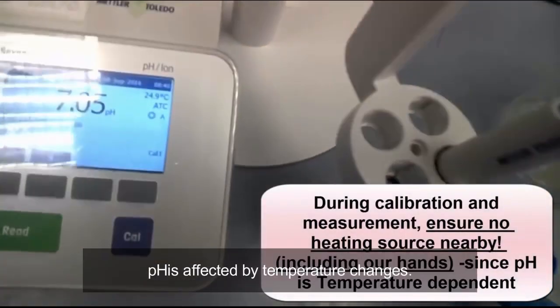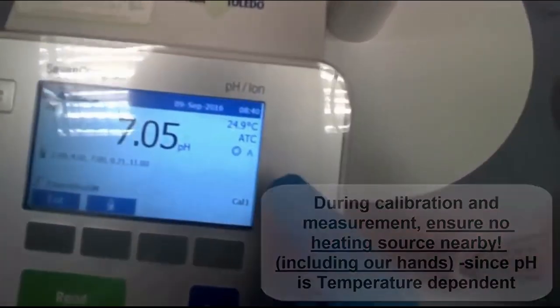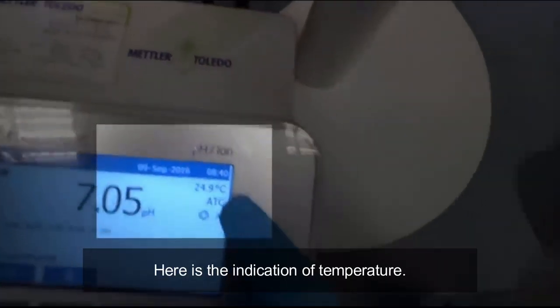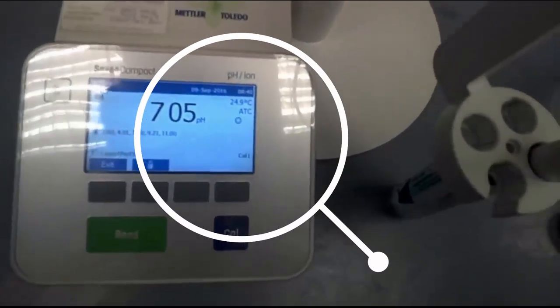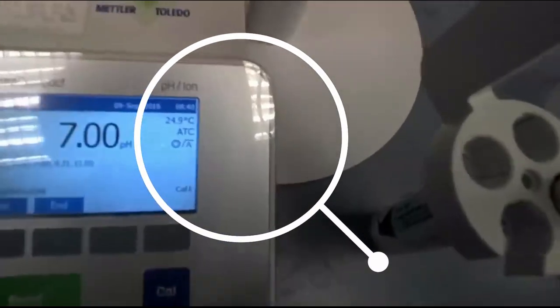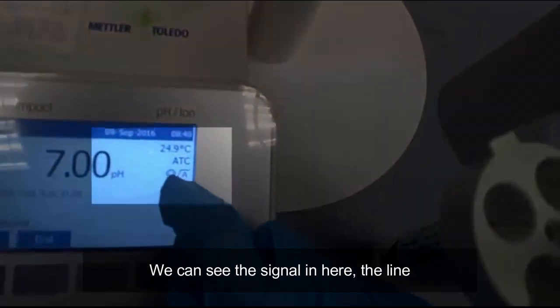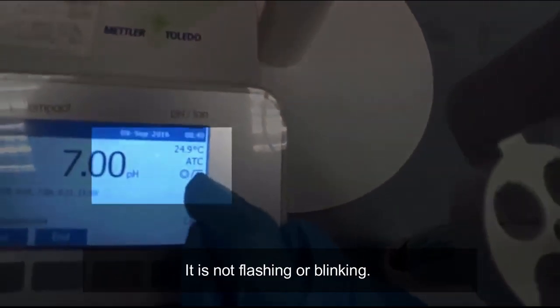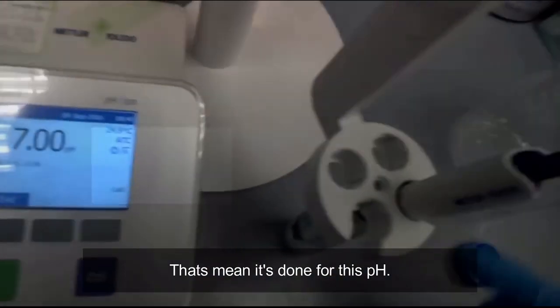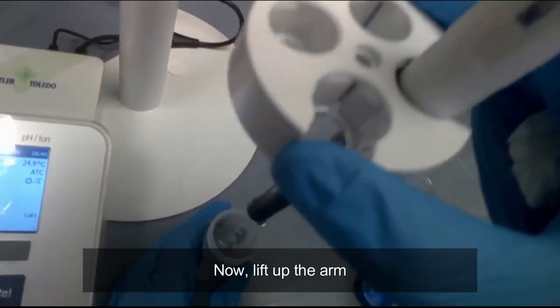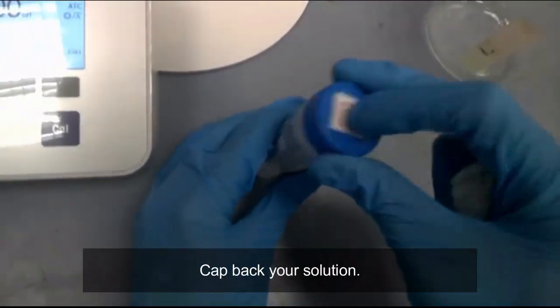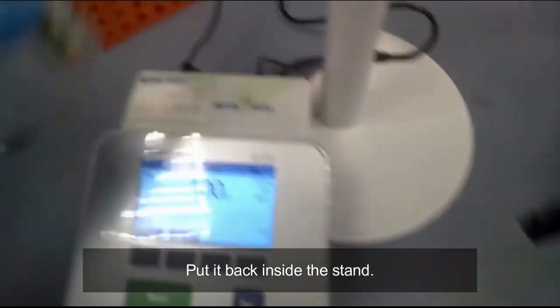Don't hold it because our hand is still warm. pH is affected by temperature changes. Here is the indication of temperature. This temperature will match your pH. Alright, so it hit the sound. So we can see the signal in here, the line. It's not flashing or blinking. That means it's done for this pH. Now lift up the arm, cap back your solution and put it back inside the stand.